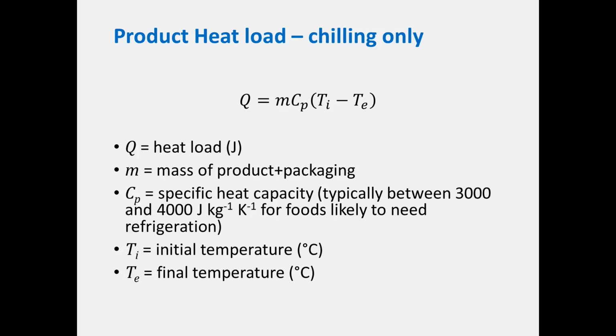So what can we say about product loads? If it's chilling only - chilled lamb, chilled beef, horticultural products - you can work out the chilling load relatively simply. The chilling load, which I've called Q, just requires the mass of the product and packaging, since that typically comes in warm as well, and the specific heat capacity. Foods likely to need refrigeration tend to have high water content, so that value will typically be between 3,000 and 4,000 joules per kilogram Kelvin. If you take a conservative value of 4,000, you just need the initial temperature, an average temperature, and the final temperature you want. These are relatively easy quantities to measure - measure the mass, the initial temperature, know the final temperature, multiply by 4,000, and that gives you your heat load fairly simply.